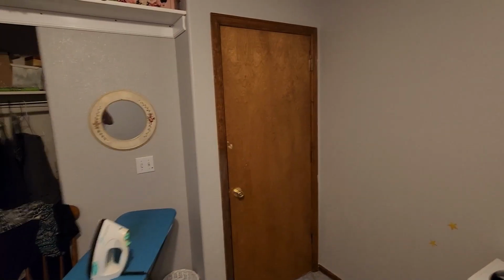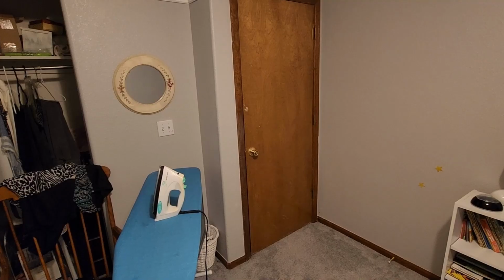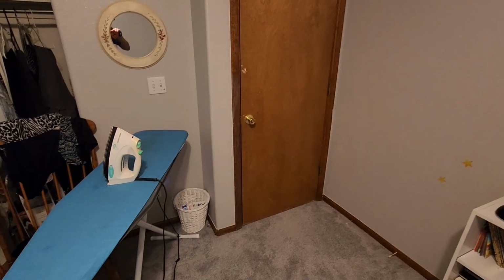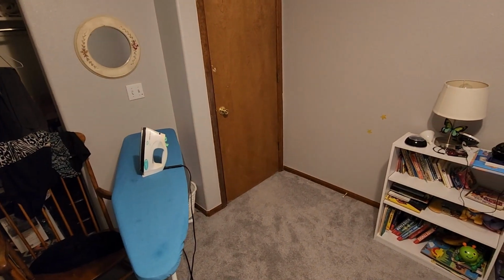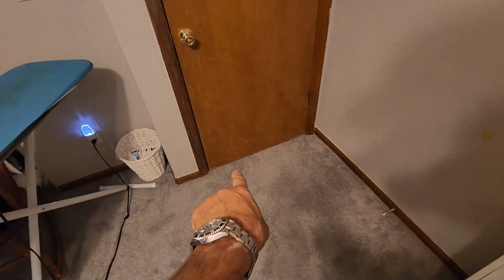While I'm in this house, I wanted to give you an example of probably why your central air conditioning is not working. So this room here has one supply duct somewhere right behind and underneath that crib. You can't pump air into this room without getting air out. There is no transfer grills anywhere. Look at the gap underneath the door. There is no gap under the door. So there's no way to pump cold air into this room.